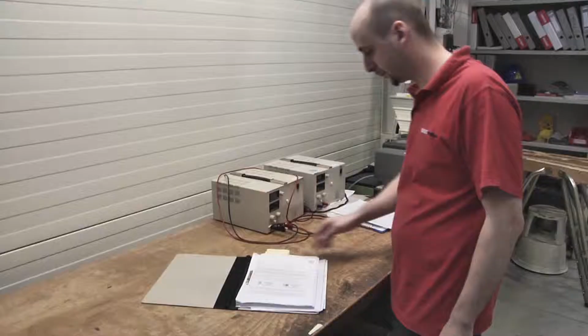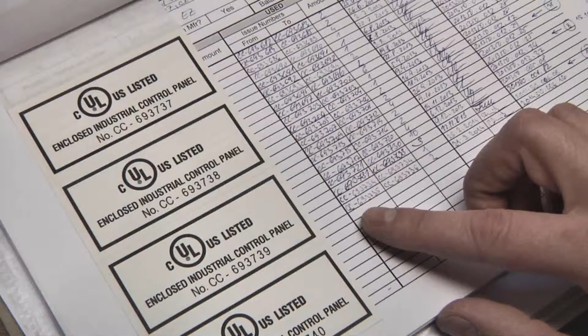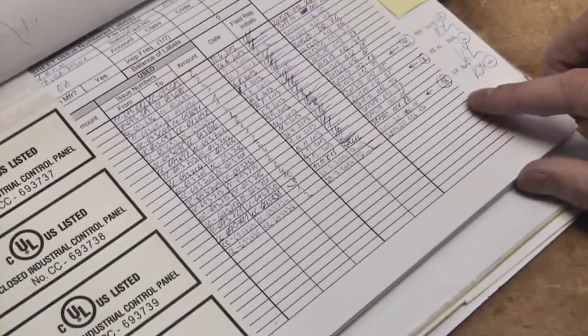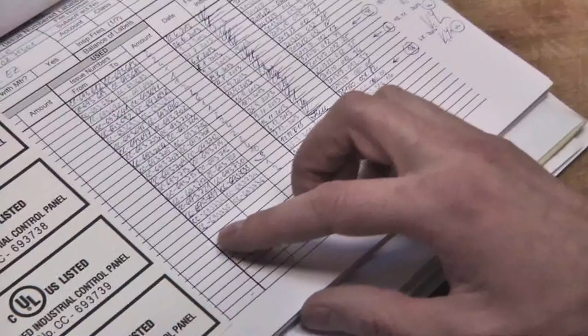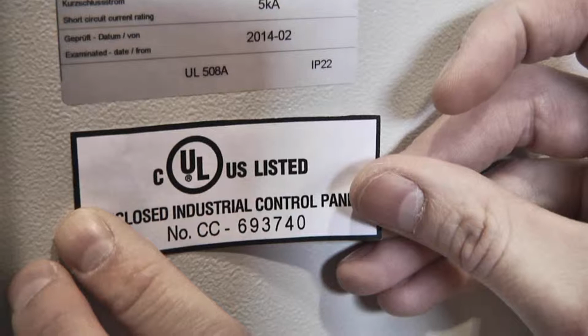If the switchboards are to form part of the equipment intended for the United States or Canada, the final inspection department checks that specific certified materials have been used, which we then confirm by attaching a certification label pursuant to the UL 508A standard. This label enables a globally accessible database to be used to trace which supplier manufactured the switchboard and whether that supplier possesses the required certification.